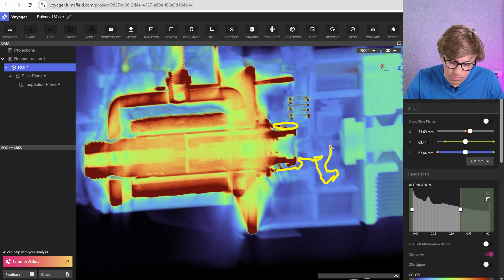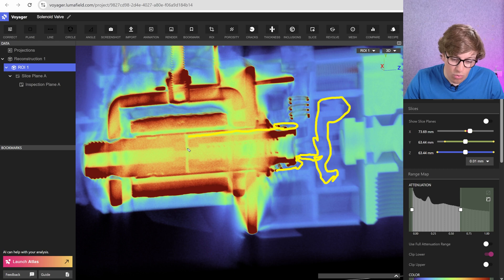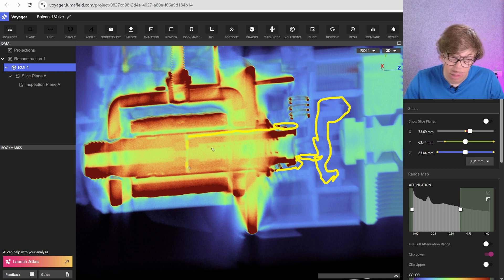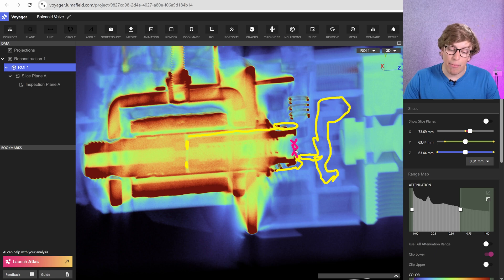A very short period of time later, this moving element reaches the end of travel and seals off this flow portion. Air can't flow down the length of this; it can only flow around the outside. So you get your gas flow stopped here, but then when you release the solenoid, now this gets shut again by spring action.